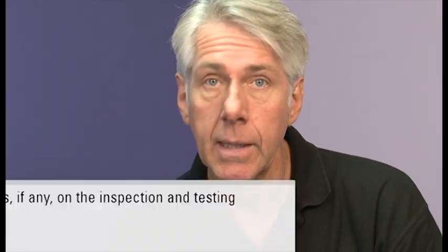Now, we'll examine this more when we look at the electrical installation condition report form. But the important word here is agreed. Any limitation must be agreed with the client, ideally before the work has even started. Before we leave the minor work certificate, as previously stated, remember, it's one minor work certificate for each circuit worked on.